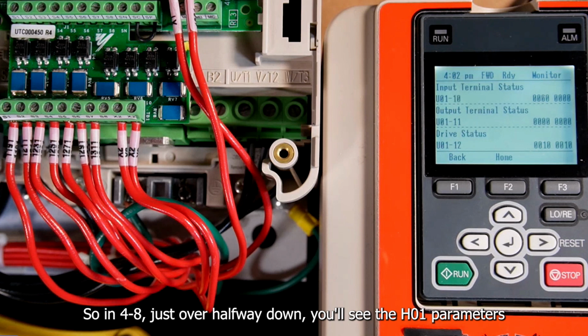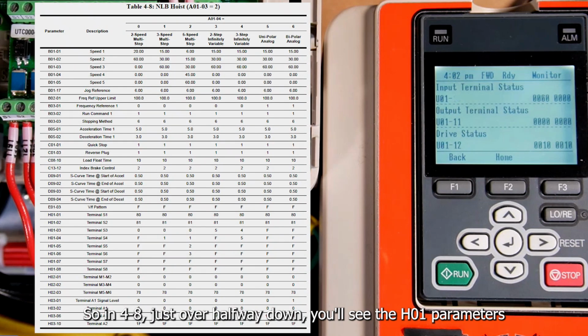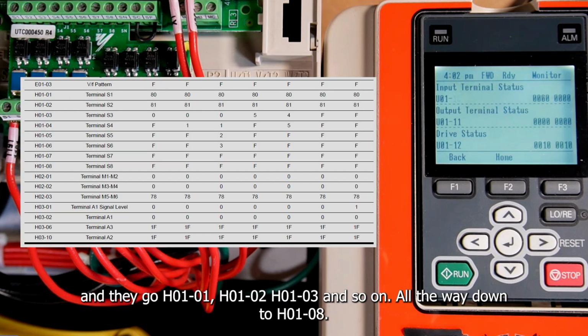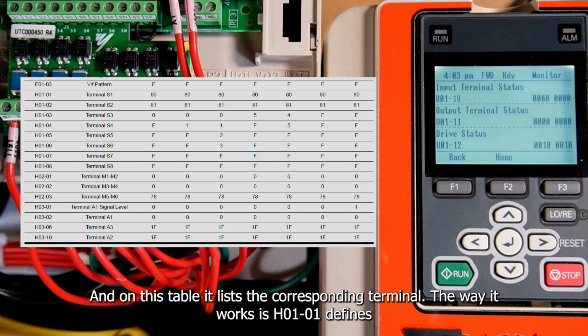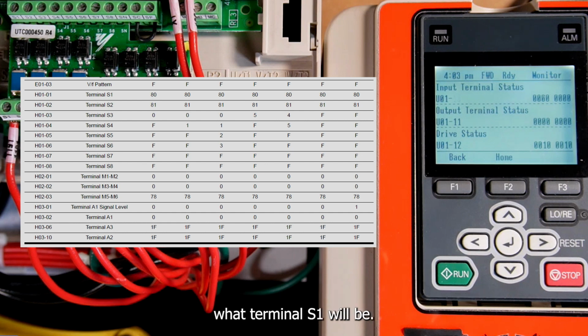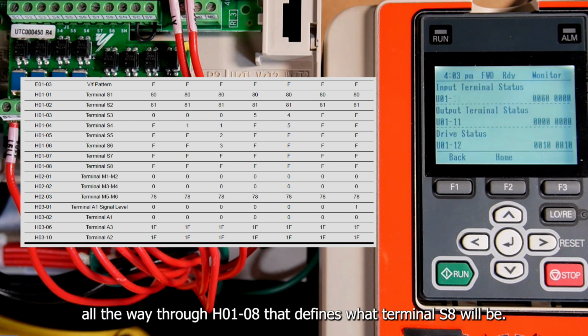So in 4-8, just over halfway down, you'll see the H01 parameters, and they go H01-01, H01-02, H01-03, and so on, all the way down to H01-08. And on this table, it lists the corresponding terminal. The way it works is H01-01 defines what terminal S1 will be. H01-02 defines what terminal S2 will be, all the way through H01-08 that defines what terminal S8 will be.